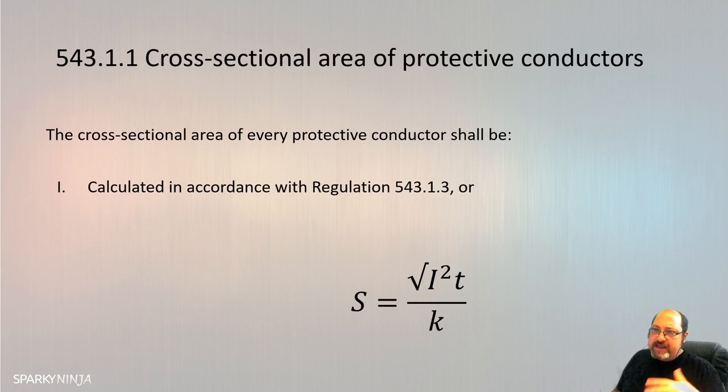In the case that we did with the 10mm twin and earth, we did this cable calculation in chapter 41, and we got to the conclusion that with the method of installation and all the rating factors that we used, we set a 10mm, and we verified volt drop. So we're going 10mm good, volt drop good.